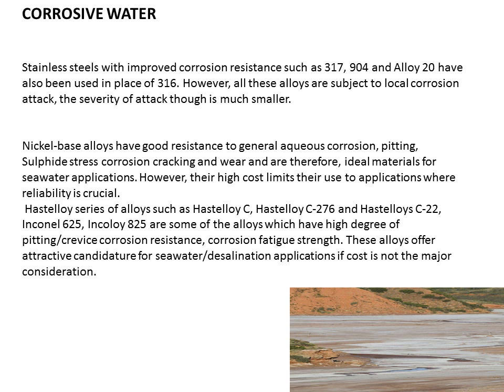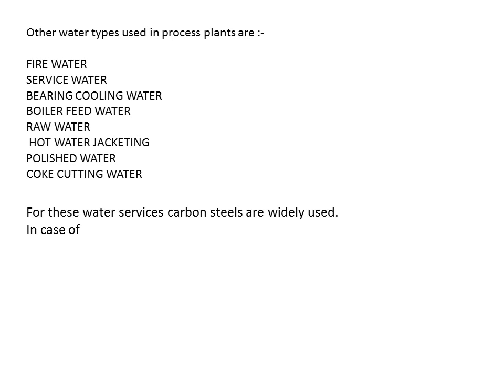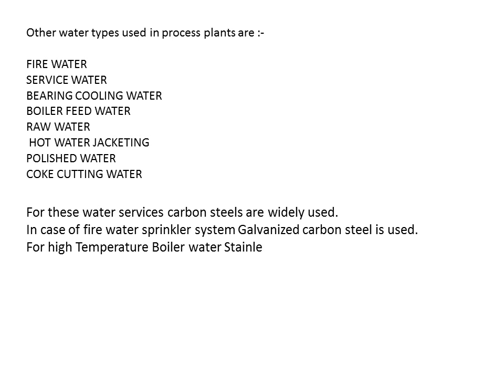Other water types used in process plants include fire water, service water, bearing cooling water, boiler feed water, raw water, hot water jacketing, polished water, and coke cutting water. For these water services, carbon steels are widely used. In the case of fire water sprinkler systems, galvanized carbon steel is used. For high-temperature boiler water, stainless steel or steel with 1.25% chromium is used. This concludes the discussion of water types and the piping materials used for various water services.